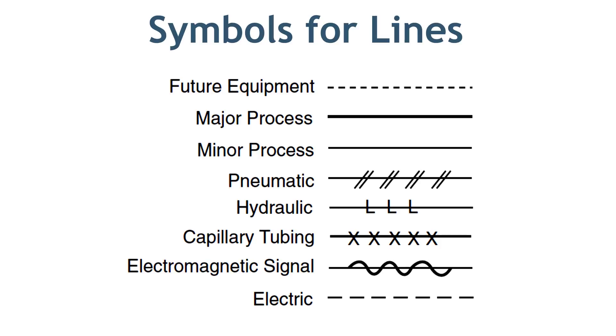This is how various lines and connections are shown on PFD and P&ID. Main process lines are shown as a dark black line, whereas minor lines are shown as thin black lines. You can see the symbols for pneumatic, hydraulic, and capillary lines also. Electric signals are shown as a dotted line and electromagnetic signals are shown as a wave on the solid line.